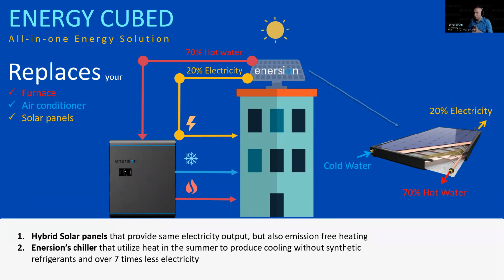If I get your question correctly, in terms of operation temperature, we prefer this to be above 85 C. Vacuum tubes can easily go to very high temperatures, even 300 degrees C, but we don't operate there — we run around above 90 C for vacuum tubes. We use a combined effect depending on where things are: a bunch of hybrid solar and a bunch of vacuum tubes. The rejected line goes at very low temperature into the hybrid solar, and once the temperature heats up, we go to vacuum tubes for that final bump in temperature.